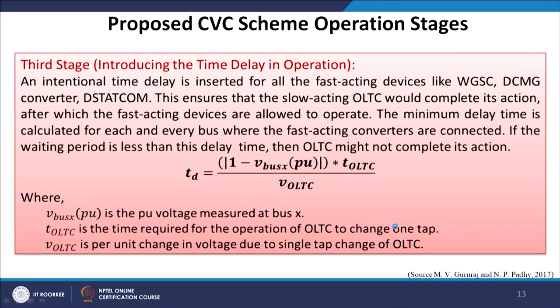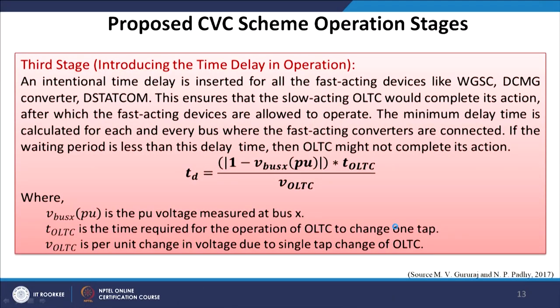An intentional time delay is inserted for all fast-acting devices like the WGSC, DC microgrid converter, and DSTATCOM. This ensures that the slow-acting OLTC would complete its action first. As discussed earlier, when all fast-acting devices act simultaneously, the slow-acting devices may not contribute much. So the slow devices like OLTC are allowed to act first, after which the fast-acting devices are allowed to operate.